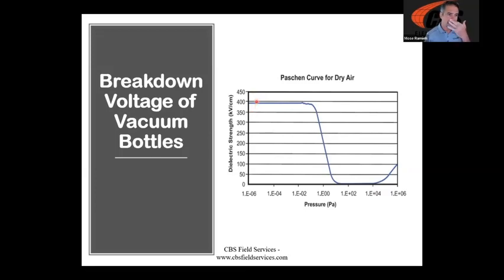This is the curve that is the dielectric strength of dry air, right? So if I've got a really good vacuum way over here at 10^-5, 10^-4, you can see we've got a tremendous amount, almost 400 kilovolts per centimeter of dielectric strength. But you'll also notice that if I'm sitting right here at 10^-2, I'm very close to going over the edge. And once I go over this edge, I go from a really high dielectric strength very rapidly to a very low dielectric strength. So our traditional test was never able to tell us where I'm at. It was always a go, no go test.